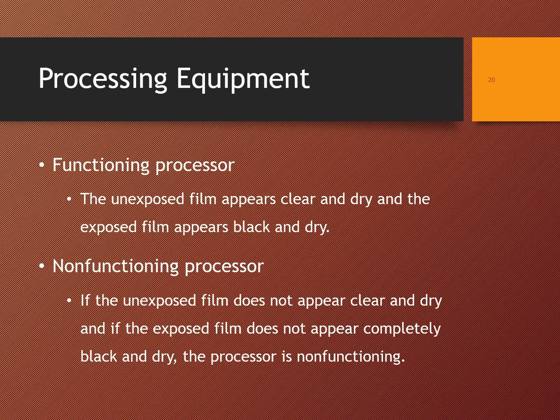If your processor isn't working properly, then the unexposed film doesn't appear clear and dry, and if the exposed film does not appear completely black and dry, then your processor isn't functioning. You'd have to figure out where the problem is.